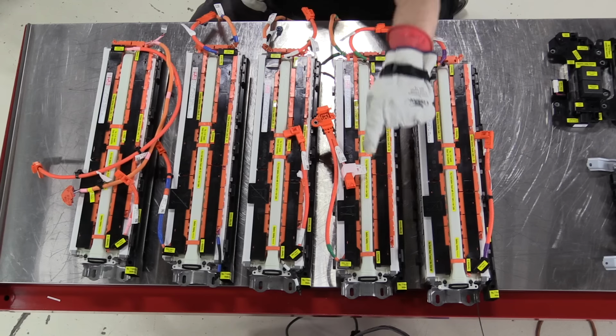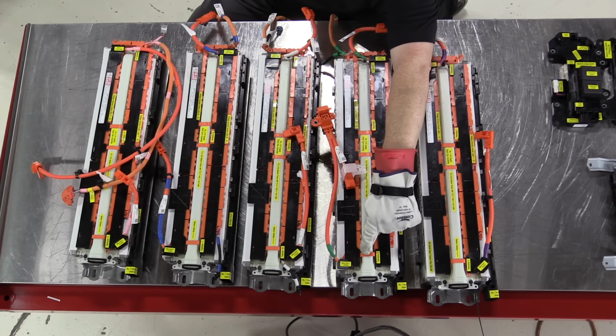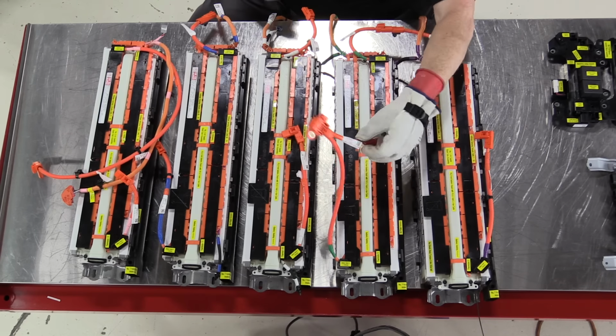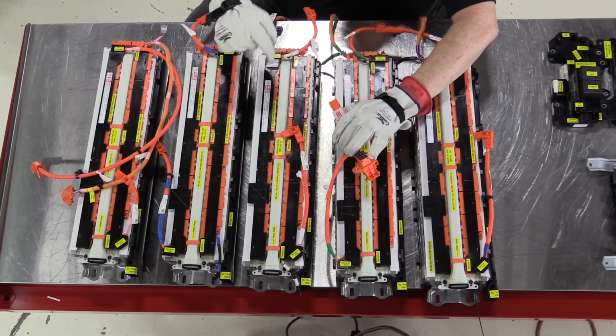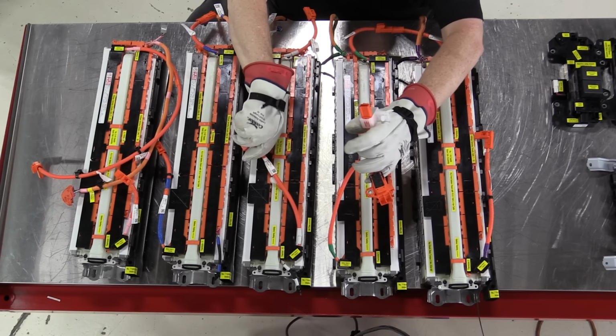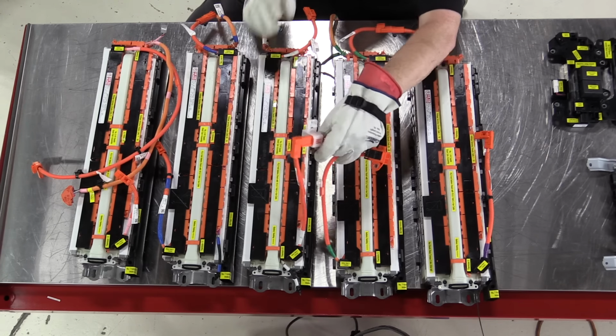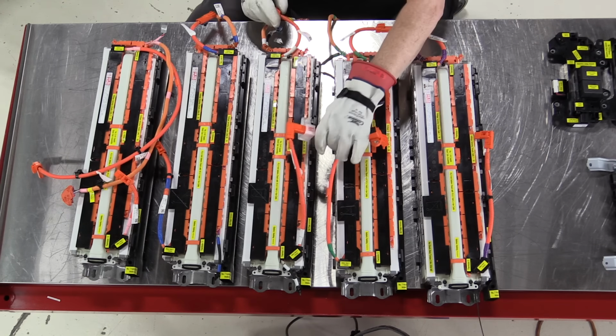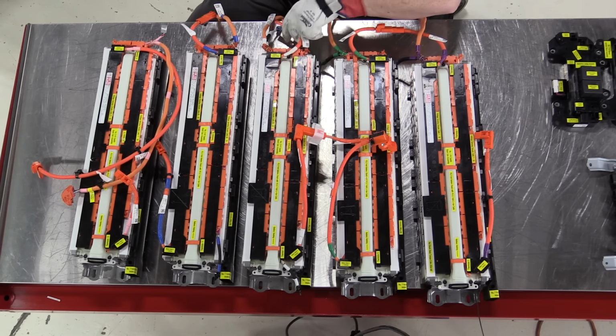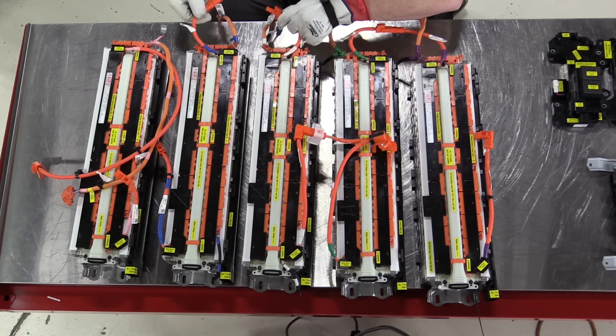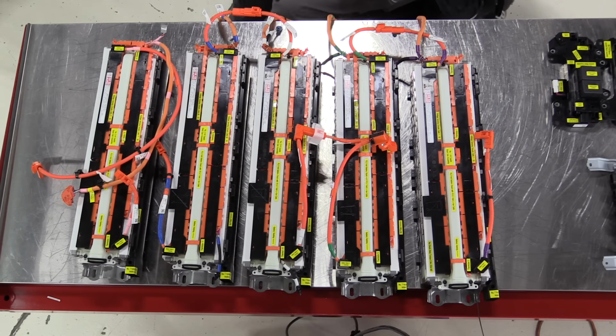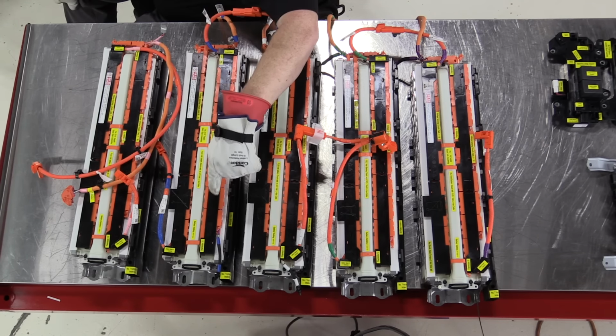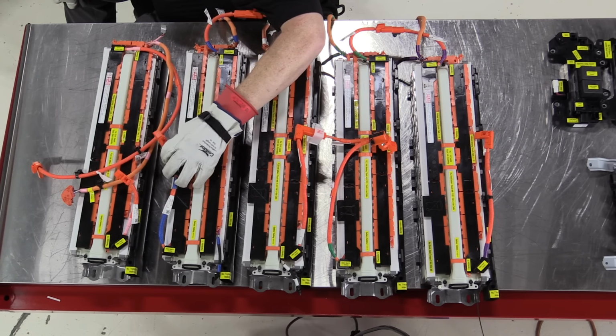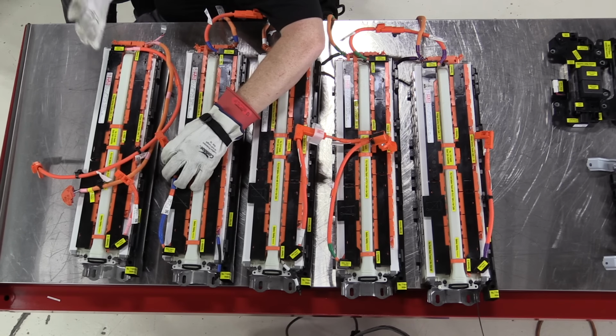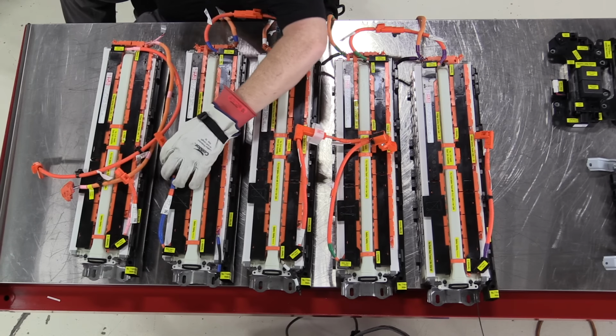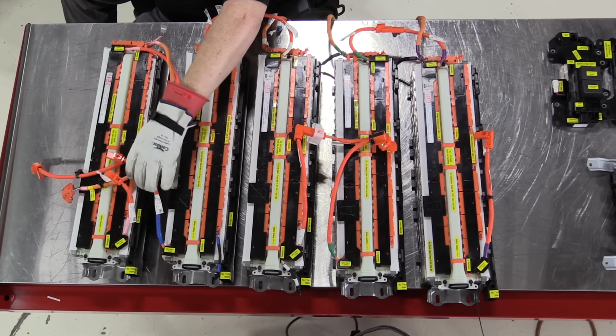The other end of battery stack number 2, which has cell number 38, has its own positive terminal that connects to battery stack number 3, cell 39's negative terminal. Those two clip together, and cell number 57 of battery stack number 3's positive terminal connects to cell 58's negative terminal. Then on the other end of battery stack number 4, we have cell 76 with its positive terminal that will connect to battery stack number 5's cell 77, except these two terminals don't plug into each other.